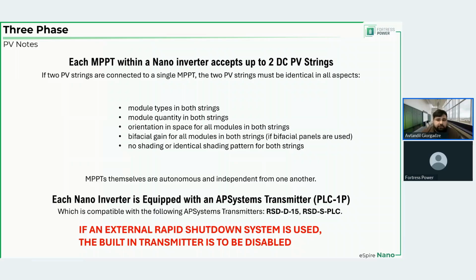I know that some of you will have a need to use optimizers instead, such as Tigo, right? And in that case, this APS transmitter may not be of use at all. If you have an external rapid shutdown system or optimizers or anything of that sort, the built-in rapid shutdown device must be disabled. Our manual will show how to do that, but to avoid crosstalk, having multiple of them working together is not allowed. You either use the built-in one or you use the external one, not both at the same time.